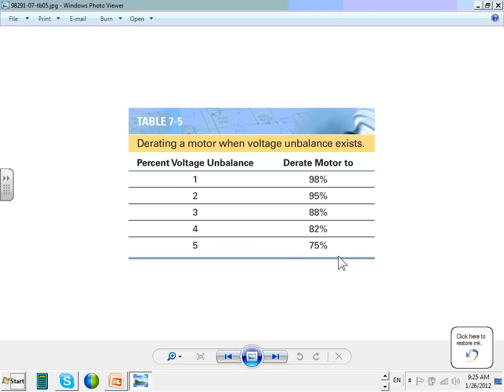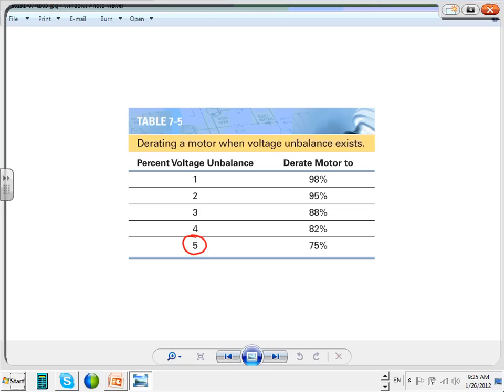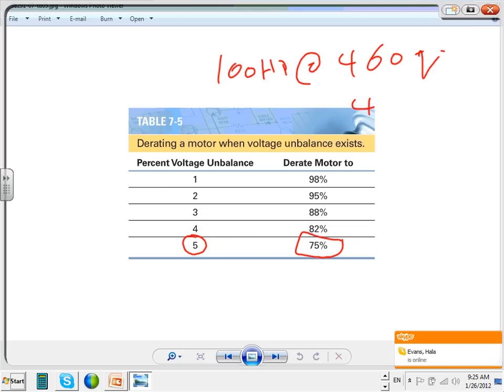Percentage voltage variance, this is what the manufacturers allow you. If you have a 5% voltage difference, you're supposed to derate your motor to 75%. You know how they solve the problem? A lot of manufacturers, if you go to the code, that will help you a lot. If you have 100 horsepower at 460 volt, anybody ever wonder why they rate them at 460? Now if you reduce it 5%, you're still okay. The system's supposed to give you 480.